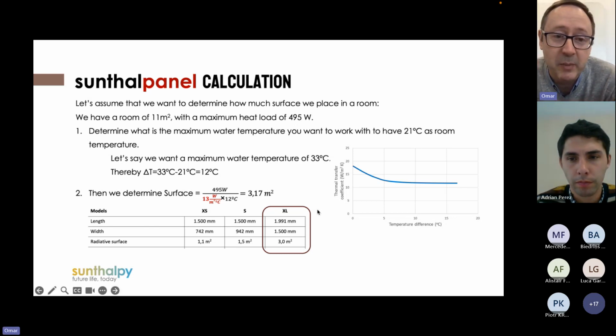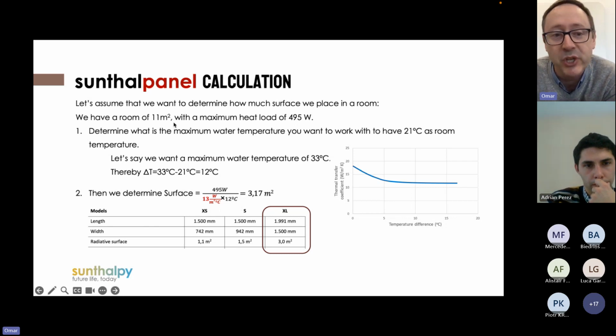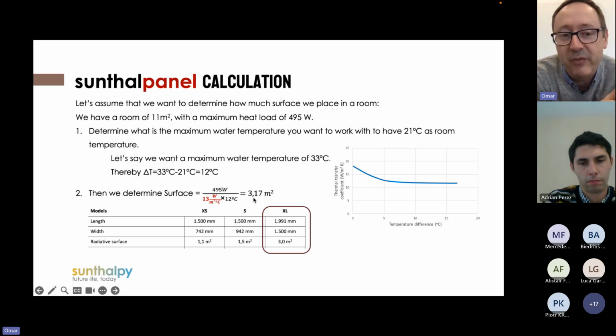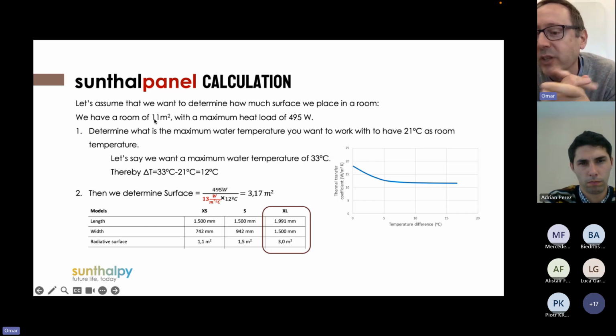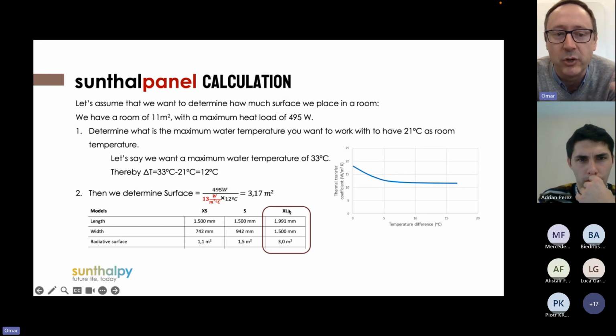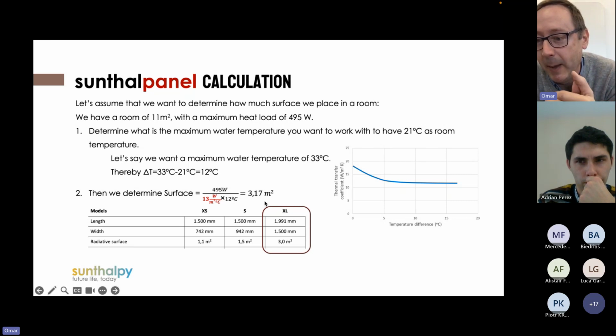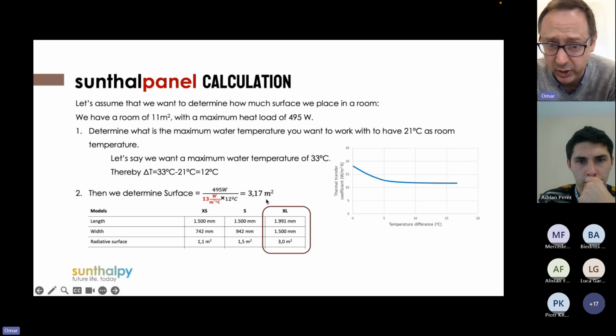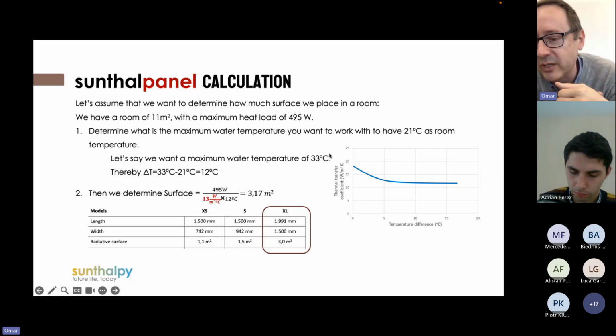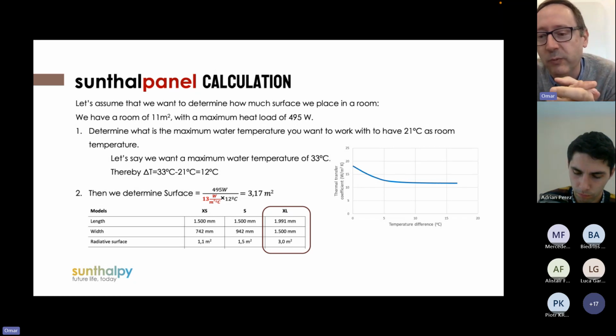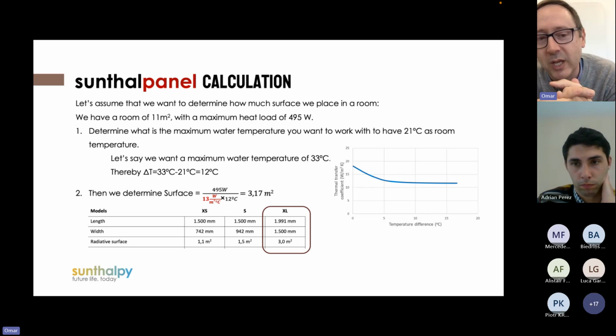Yeah, exactly. Well, basically, as we explain, this is the procedure. If we have a small room, let's say a bathroom, usually you will have to use an XS or an S. Let's imagine that instead of an 11 square meter room, we have a living room which is 20 square meters. Usually you will have to use 2 of these, or 1 of these and 1 of these, depending on the calculation. The procedure is to follow this simple calculation, basically. So you mark your objective. The key point is what is the maximum temperature you want to define for heating or cooling. As I said before, for southern countries, the key calculation factor would be the cooling load that you want to achieve with this radiant system.